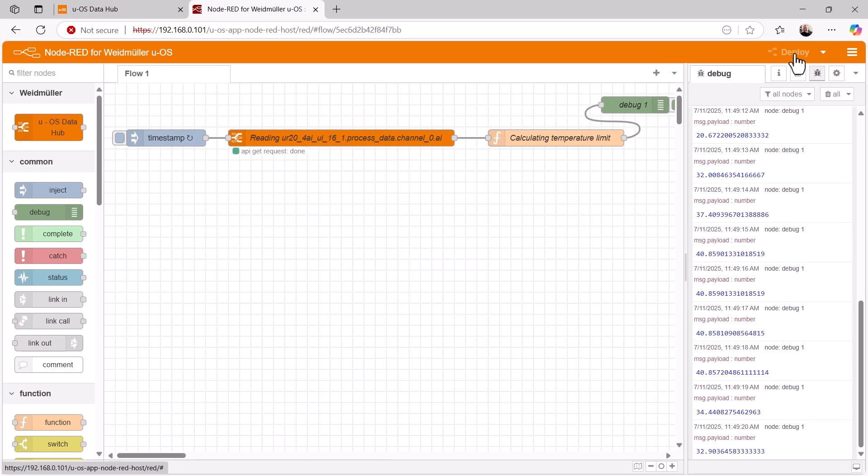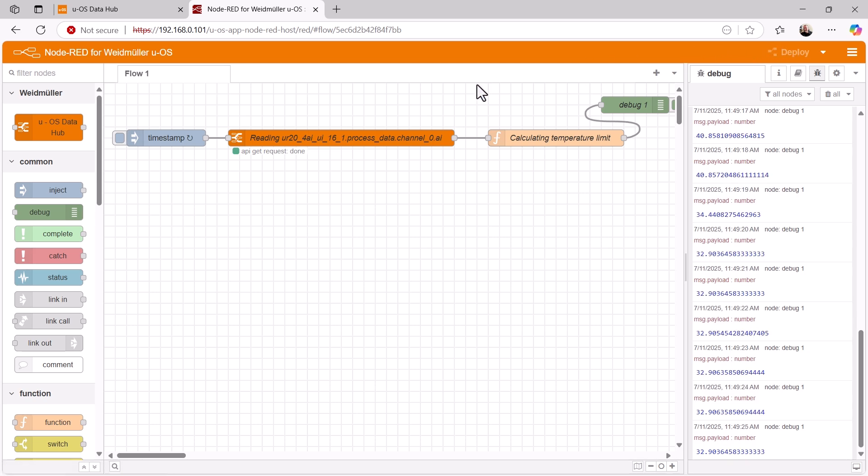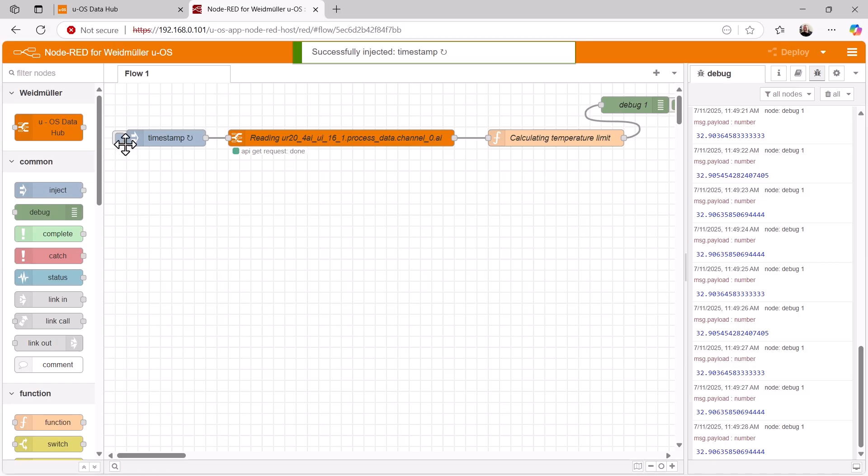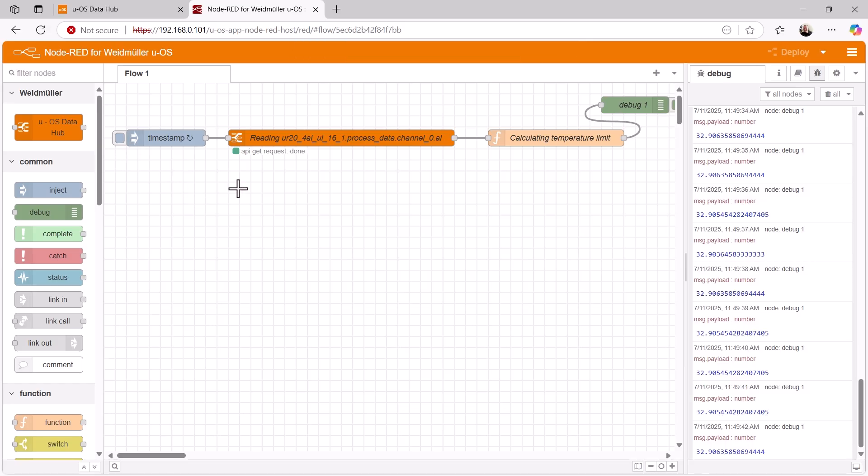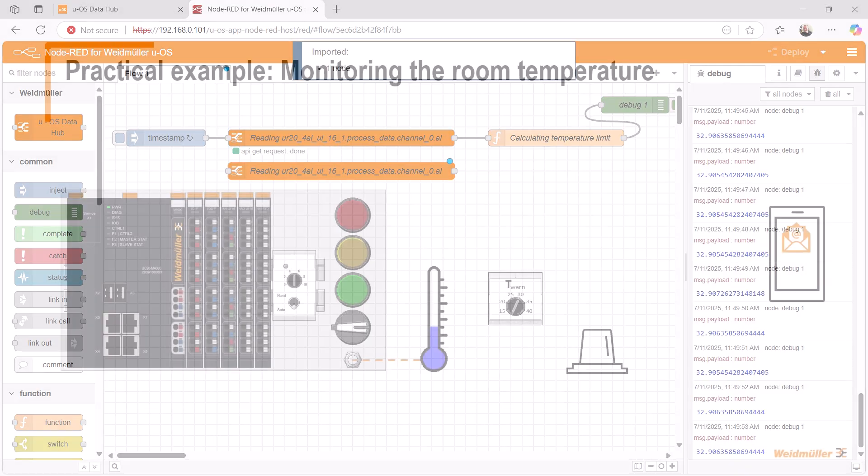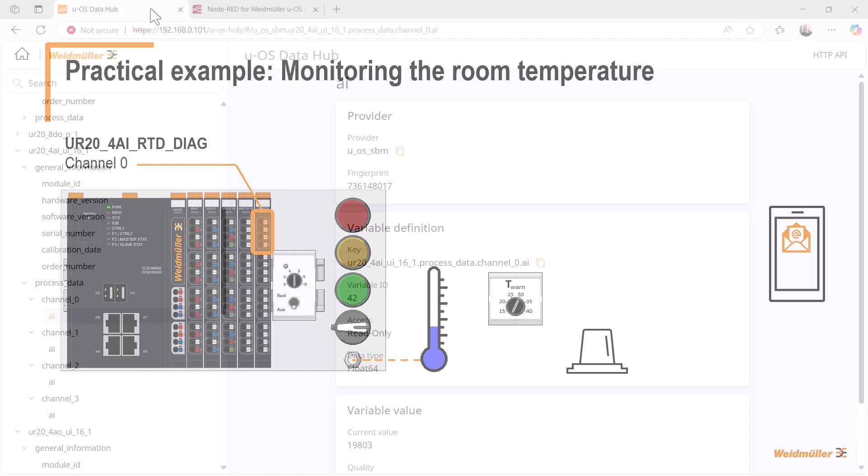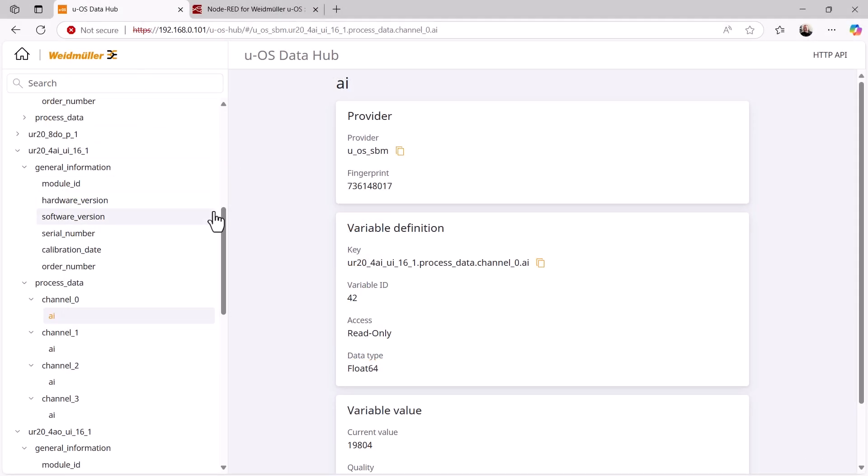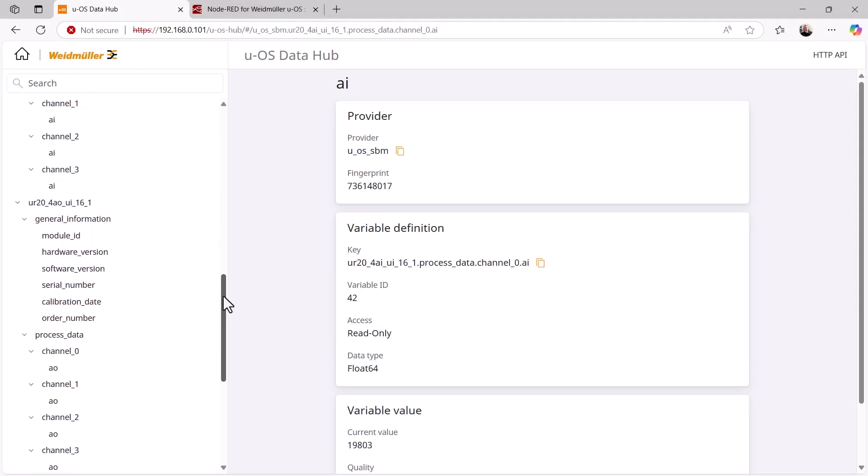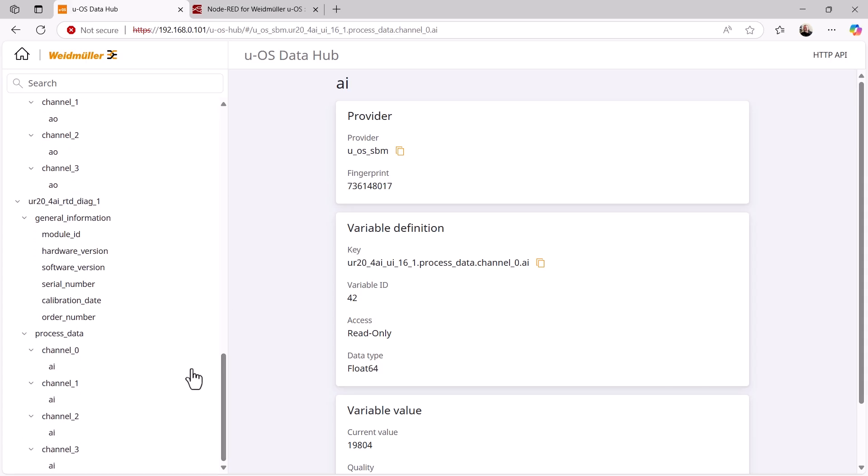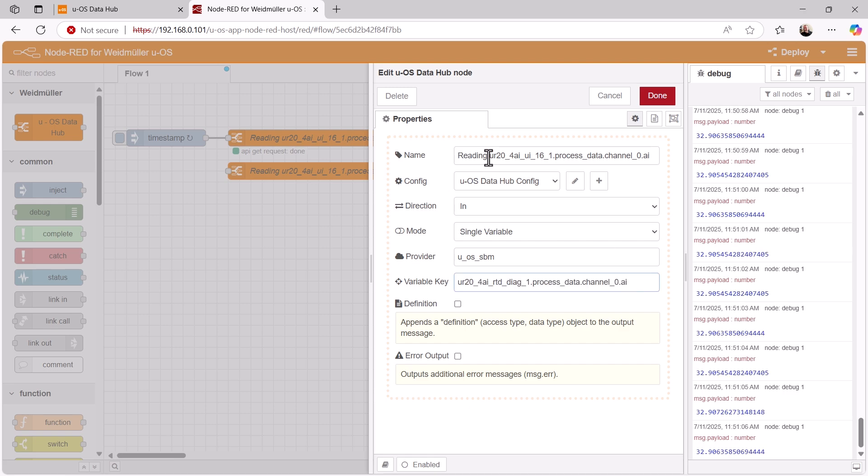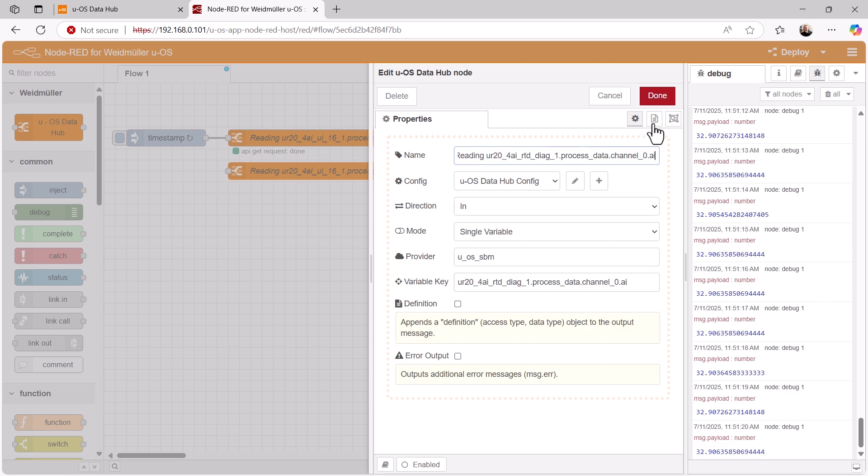Next, we retrieve the temperature value from the PT100 via the DataHub. Since this node is similar to the one used to read the potentiometer value, I copy this node and simply change the variable key in the properties. As we recall, the PT100 is connected to channel 0 on the analog input module UR20 4AI RTD diag. So we look for the corresponding analog input in the variable list and the associated variable key is displayed. We now copy it and paste it into NodeRED in the properties window. Finally, we also adapt the name of the node and that's it.